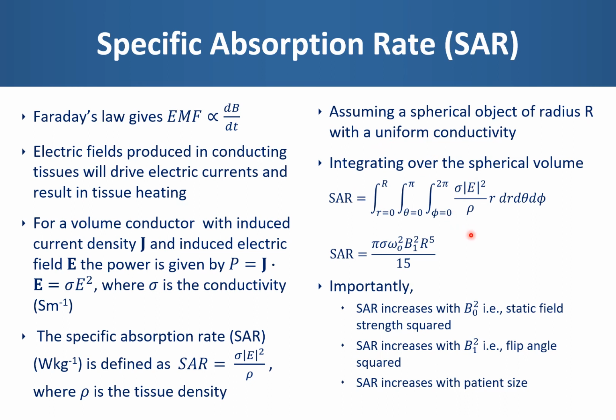Integrating over the spherical volume results in a fairly standard equation that is used to describe SAR. The important thing with SAR is to note, first of all, that SAR increases with omega naught, or B naught squared. That's to say, the static field strength squared. So going from 1.5 Tesla to 3 Tesla results in a quadrupling of the power deposition for a given RF pulse. Similarly, SAR increases with the flip angle squared. So going from a 90-degree pulse to a 180-degree pulse also results in a quadrupling of the power deposition.